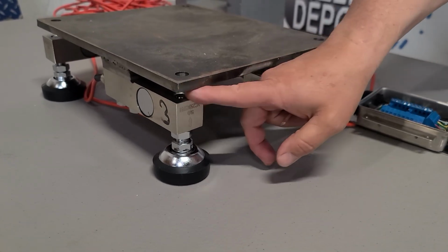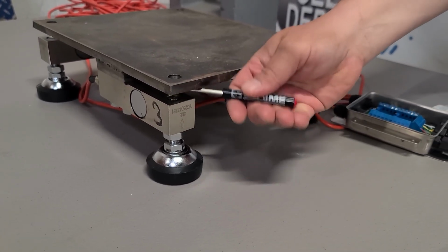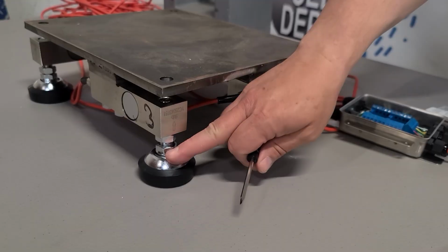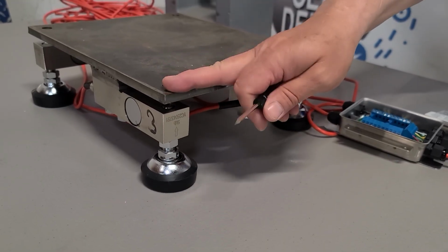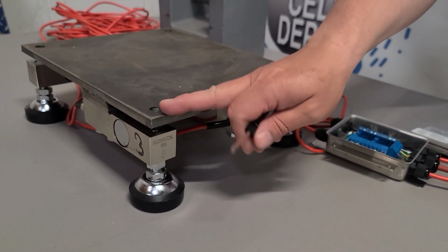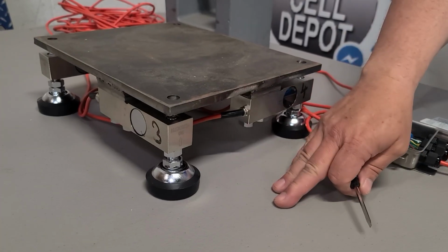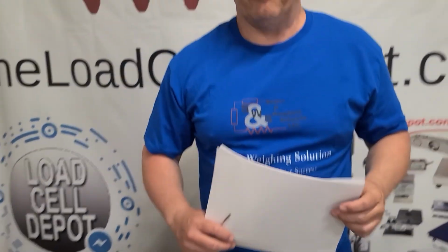This gap is very important to have there. If the foot stem touches the top plate, or the entire load cell touches your top plate, it's not going to weigh — it won't have any effect on the weighment. You're just going to have an error.